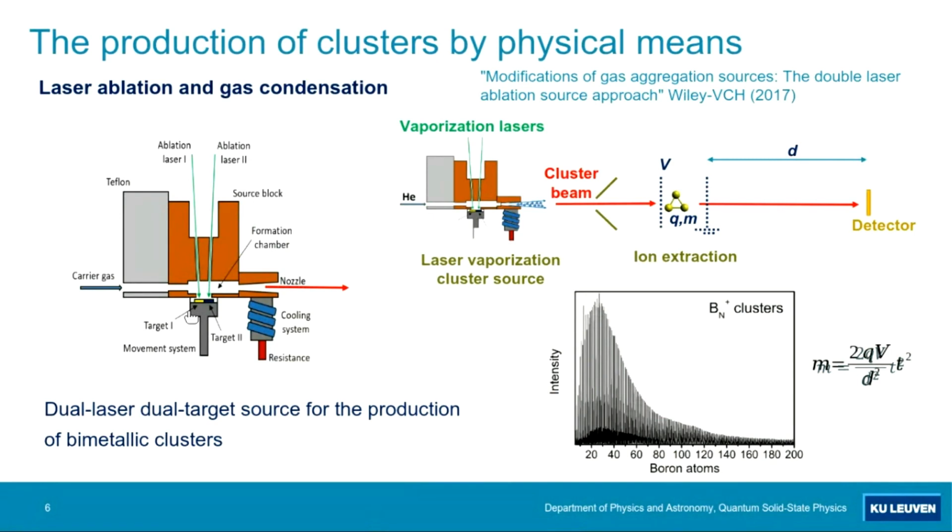But they have so much kinetic energy, you really produce a plasma by laser ablating, that these atoms will not interact with each other. And even if they form a particle, they will have so much energy that it will fragment immediately. So what we do is, right before we excite the system with a laser, we introduce what we call a carrier gas, normally helium, at a very high pressure into a very small volume where this plasma is produced, here, if you see it with this hand.